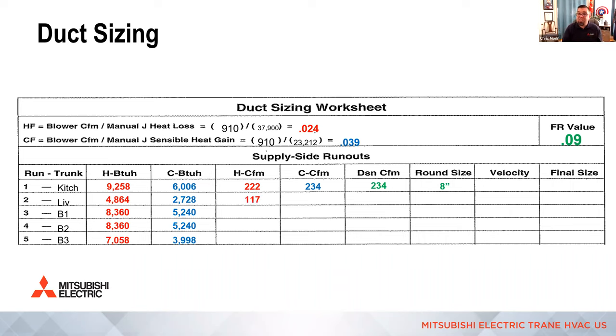And then I would walk through the same for the other rooms. Living room heating heat loss times heating factor gives me 117. Cooling gains, sensible, times cooling factor gives me 106. The higher of the two is 117. That ends up being a 6-inch. And we do the same for all of them, right? Then we go back and verify velocity. It's really important. Don't omit that.